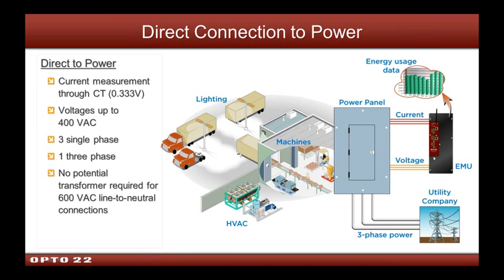Now, what voltages can we handle? Some of you might be familiar with our AIPM modules or AIPM3, which could handle up to 220 volts. With the OptoEMU sensor, we've taken that to a higher voltage capability. So the electronics can handle up to 400 volts AC. So, for example, we could do as high as 600 volt systems. So 3-phase in the US at least, the common voltage is typically about 480 volts. So the way we handle up to 600 volts is we do a line to neutral measurement, and in a Y configuration, line to neutral at 600 volts, for example, is 347. Thus you see the 400 VAC. On a 480 volt system, line to neutral is 277. So you can see we don't need an external potential transformer. You can go directly with up to 600 volts line to line.